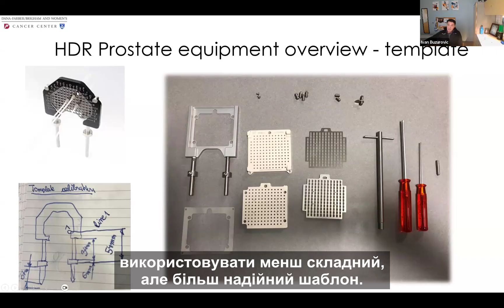Here you can see my sketch for a calibration, and I'm going to talk briefly about the calibration of the ultrasound system for prostate brachytherapy. We basically have three templates: the physical Martinez template in this case, the virtual template in the treatment planning system, and the ultrasound template. So the role of the physicist in calibration of these three pieces of equipment is to make sure that all these templates correspond to each other. That means that when the needle is inserted in, let's say, D2, the needle should show up in the ultrasound and in the treatment planning system at the same place.